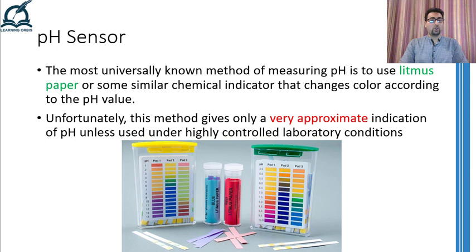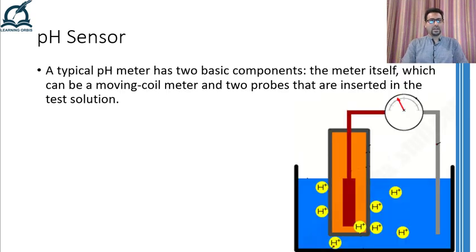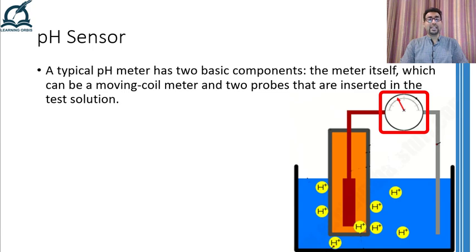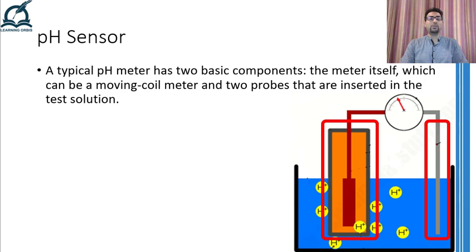Therefore, we have to resort to some other more accurate and automatic method for measuring the pH if we want to get this measurement in an industrial environment. A typical pH meter has two basic components: the meter itself, which is basically a galvanometer but has a scale drawn on it so that it shows the pH value, and two special probes that are inserted in the solution whose pH is to be measured.